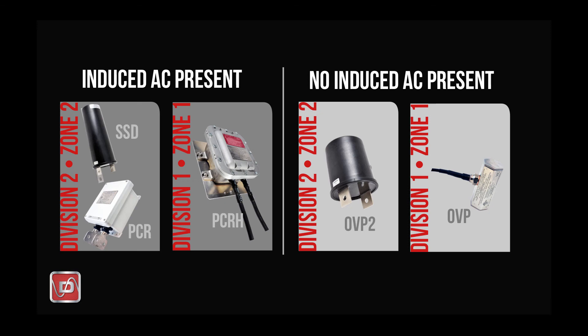Locations that tend to be Div 1 or Zone 1 could include refineries, airport fueling systems, gas processing plants, or other locations where explosive gases are vented. Using this chart, you can easily select a product family based on these two criteria. An AC mitigation project, for example, typically uses a Div 2 or Zone 2 product, resulting in a choice between the PCR and the SSD. Both of these products can be used by default for most applications if it's a Div 2 or Zone 2 site. For applications that do not involve induced AC, such as insulated joints within airports or plants, the OVP or OVP2 can be used.